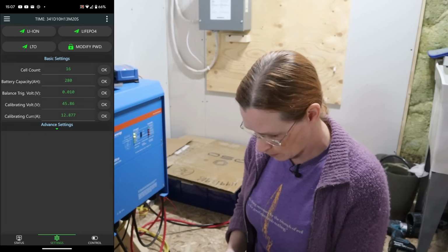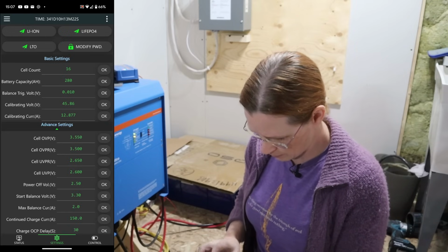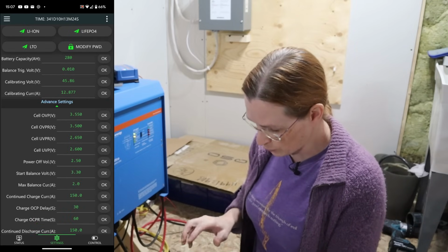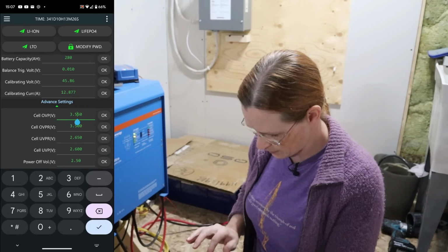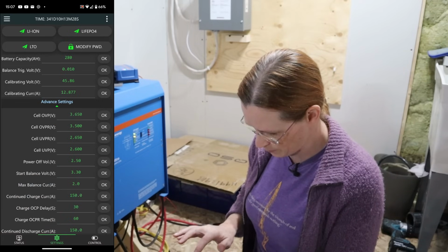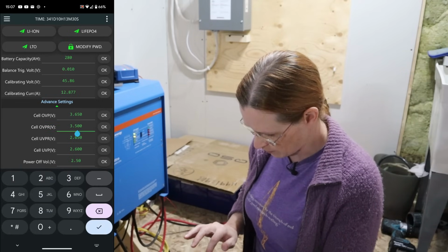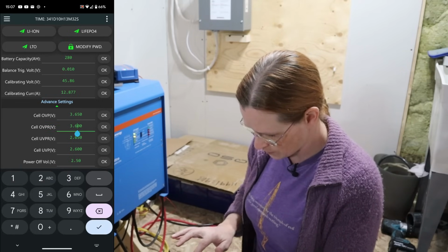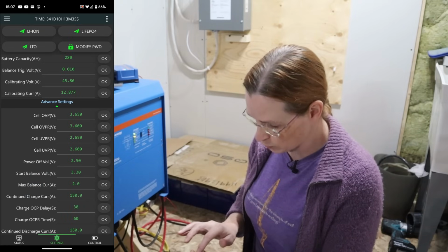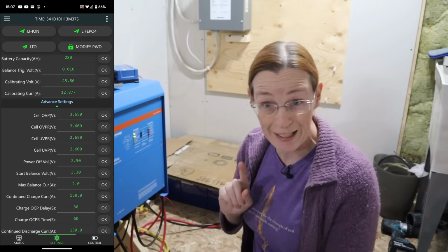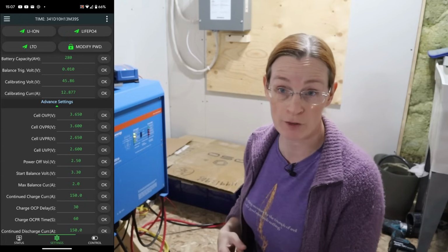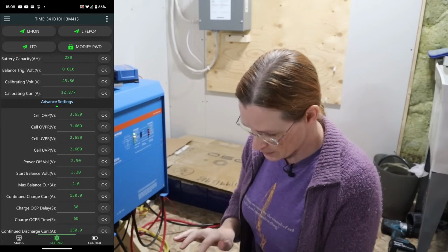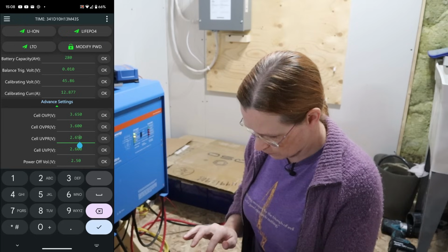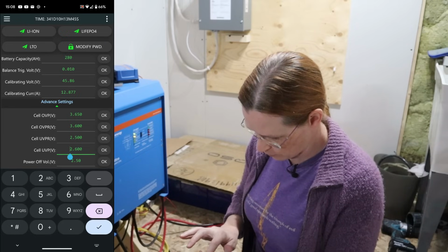Right, so let's go into advanced settings. I had the cell over voltage set to 3.55. Let's set that to 3.65 like it was before, and we'll set the return to 3.6. The under voltage protection was set to 2.65, which I did not hit because the inverter turned off too soon, so I'm going to set this to 2.5 as I had it before.